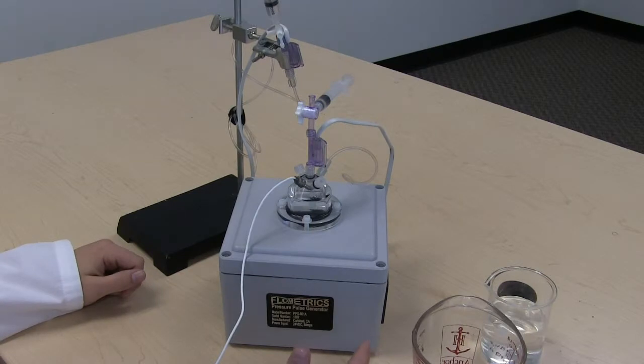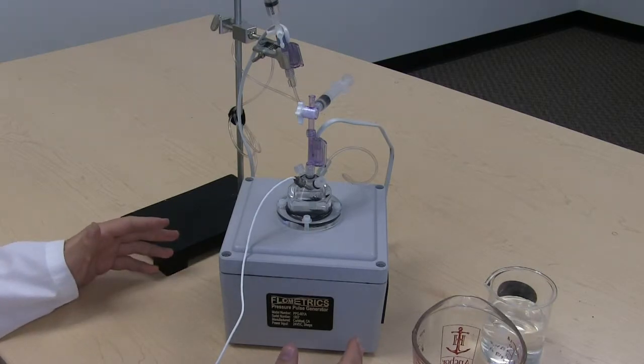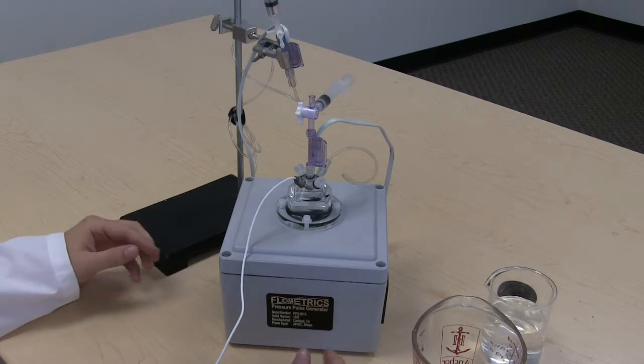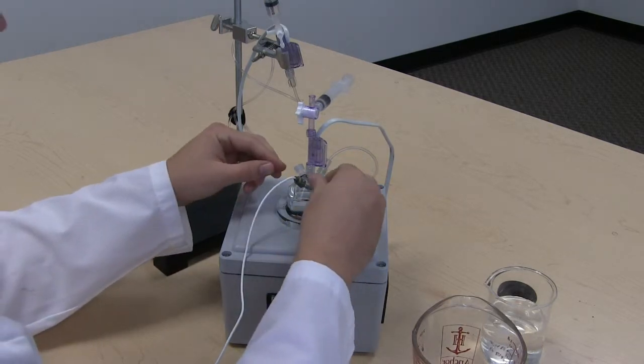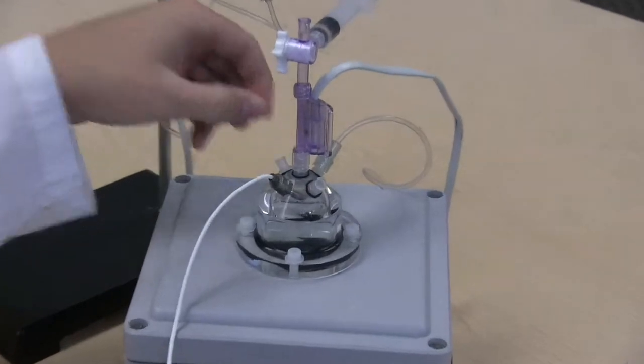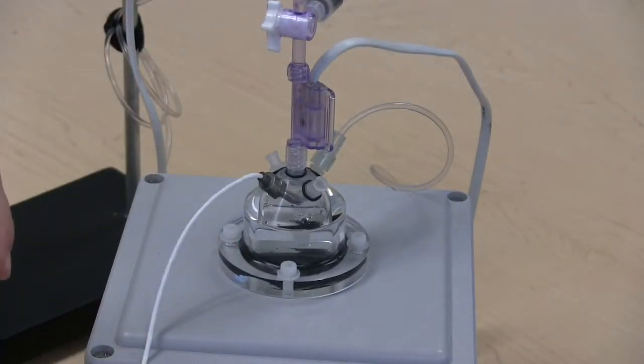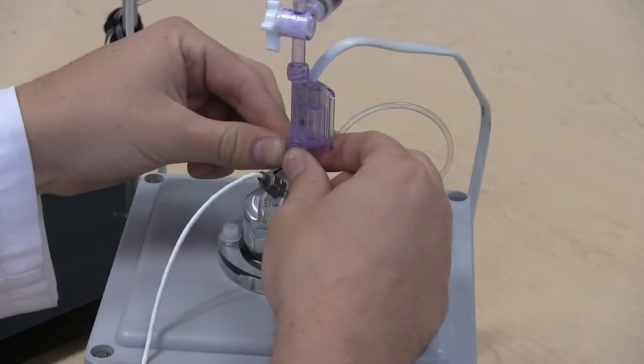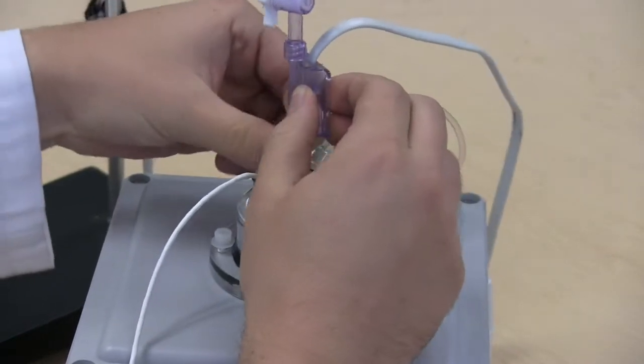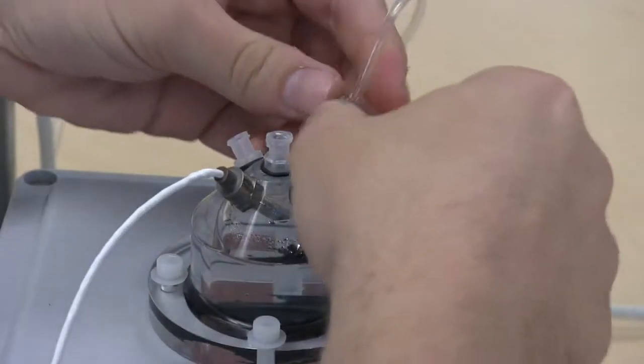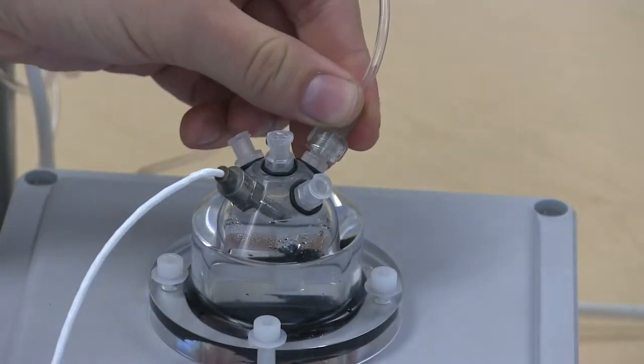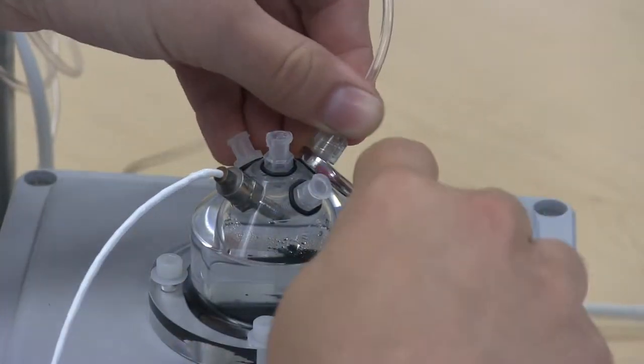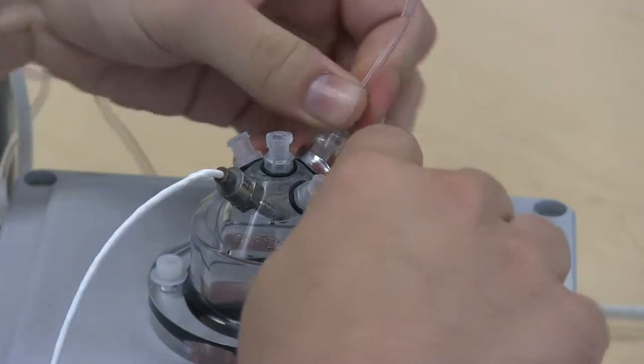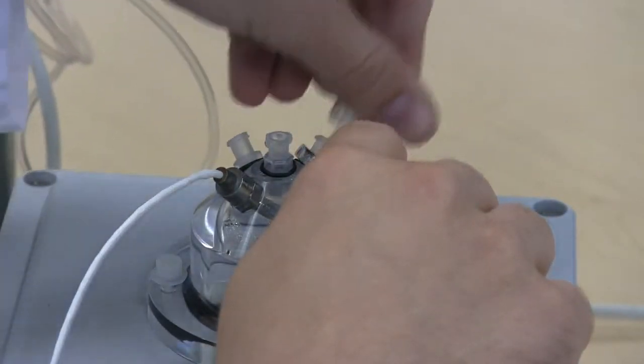This is a typical setup of the Flometrics pressure pulse generator. The first thing we're going to do to empty the chamber in the PPG is to remove each of the caps and then each of the pressure transducers or catheters that we have connected. You may want to use a wrench to hold the fittings in place while disconnecting the luer lock connections.